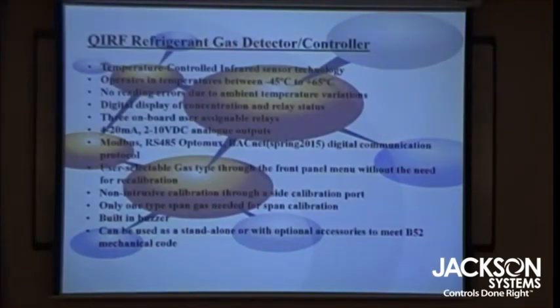The other thing is that we heat our sensor for 2 reasons. One is to prevent any humidity condensing or any condensation inside the optical bench. And 2 is that the IR sources are thermally dependent. So if you have cold temperatures, your light isn't going to shine as much, and you're going to see an increase in reading. Our competitors use plastic benches, which they can make as shiny as a metal one. The problem is you can't heat them. You can't prevent condensation, and you can't really heat plastic to a constant temperature, only to that localized spot. So there we actually have an advantage.